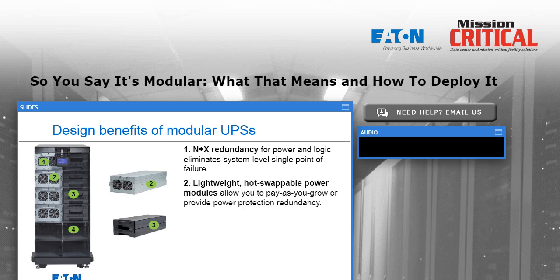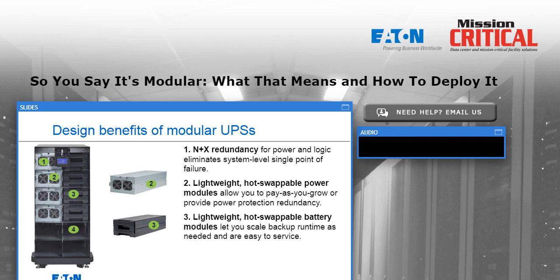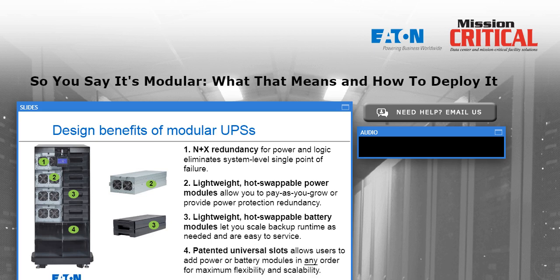The power modules now are relatively lightweight. These are transformer-free UPSs, which saves quite a bit on weight and size, and that's part of the reason we're able to have modular UPSs like you see here, and it allows you to scale that power on an as-needed basis. Hot swappable battery modules. It says lightweight here, and they're still heavy, but at least they're manageable by a single person as opposed to those multi-thousand-pound battery cabinets that you may be used to in larger UPS systems. So the backup runtime can scale just like the power capacity, and the user has the ability to change the plan sometime down the road without having to start over with a new, larger, or smaller UPS system.